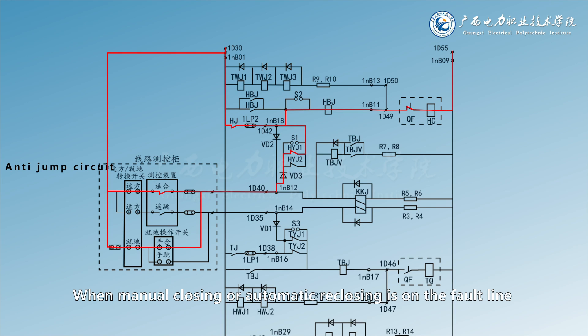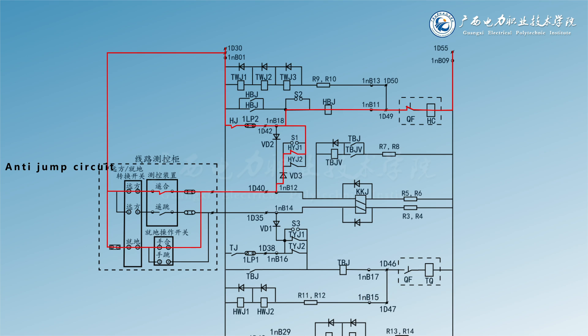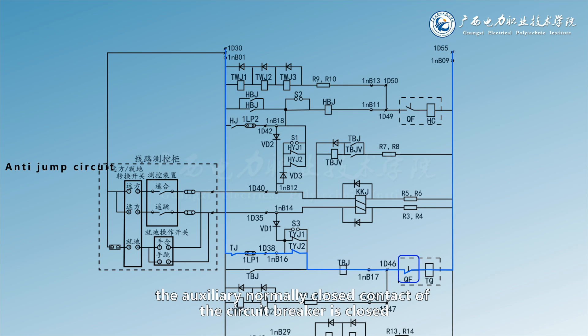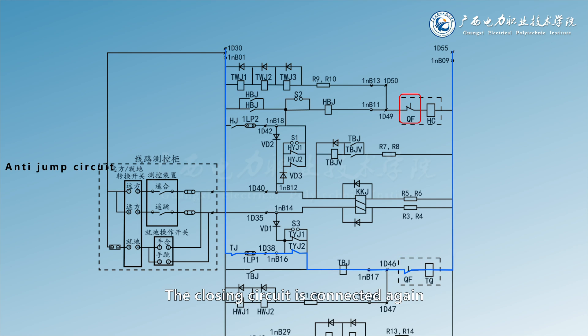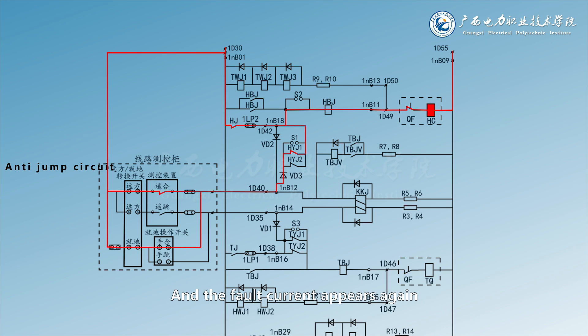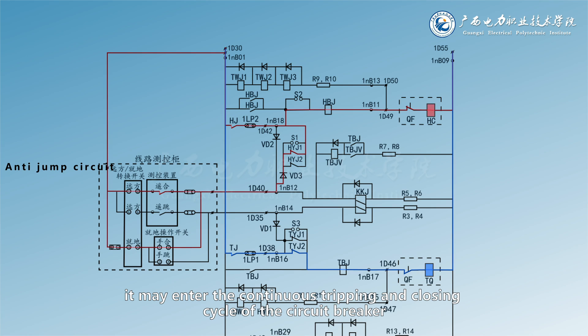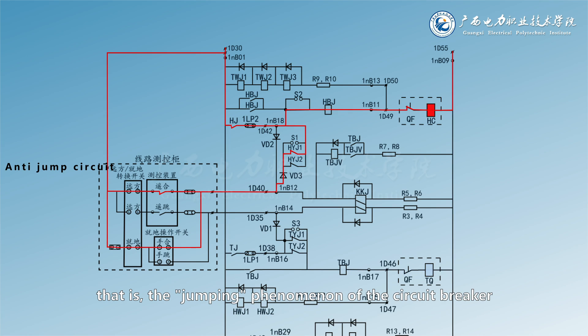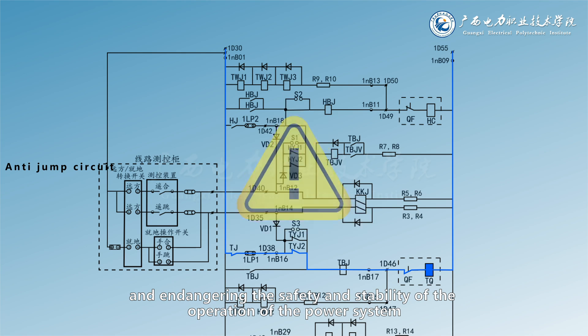When manual closing or automatic reclosing is on a fault line and the closing pulse is not released for some reason, after the protection trips the circuit breaker, the auxiliary normally closed contact of the circuit breaker is closed. The closing circuit is connected again and the circuit breaker is closed again immediately, causing the fault current to appear again. The protection will trip again. If repeated, it may enter a continuous tripping and closing cycle — the jumping phenomenon of the circuit breaker — resulting in damage or even explosion of the circuit breaker and endangering the safety and stability of the power system.